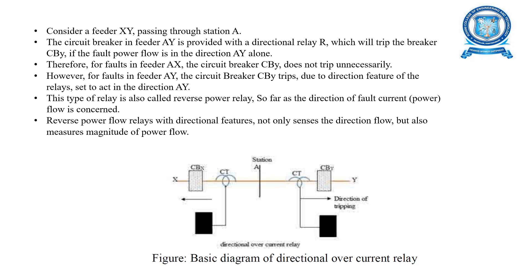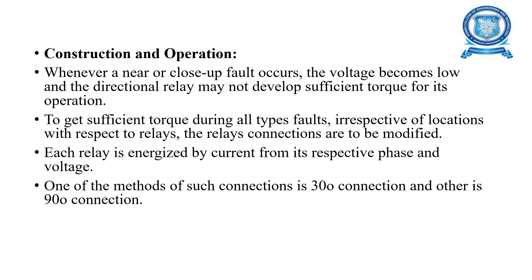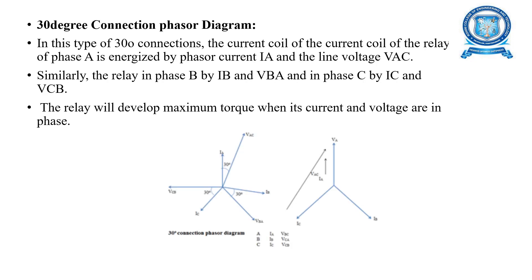For faults in feeder AY, the circuit breaker CBY trips due to the direction feature of the relays. This type of relay is also called a reverse power relay. Regarding construction and operation, whenever a near or close-up fault occurs, voltage becomes low and the directional relay may not develop sufficient torque. Each relay is energized by the current and voltage from its respective phase. Two common connection methods are the 30-degree connection and the 90-degree connection.